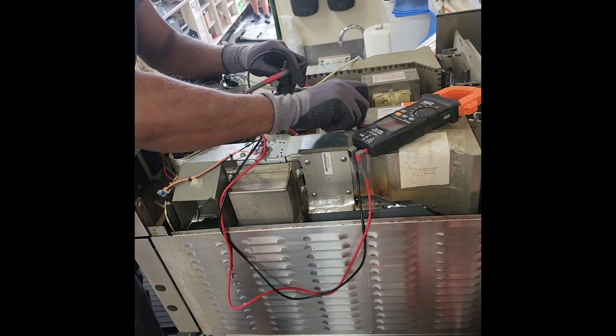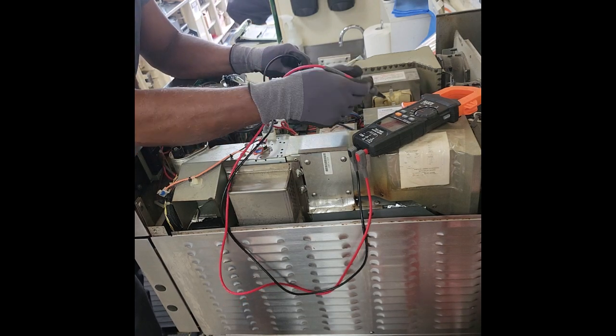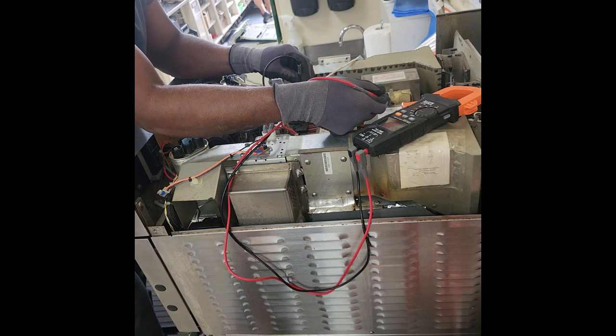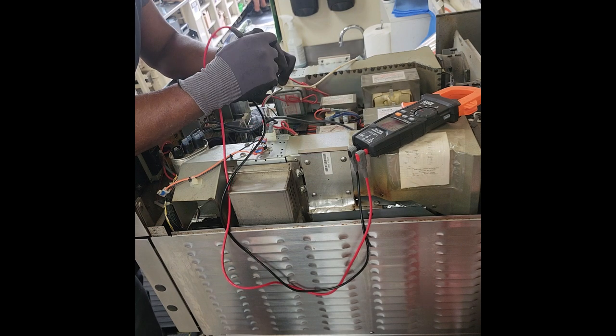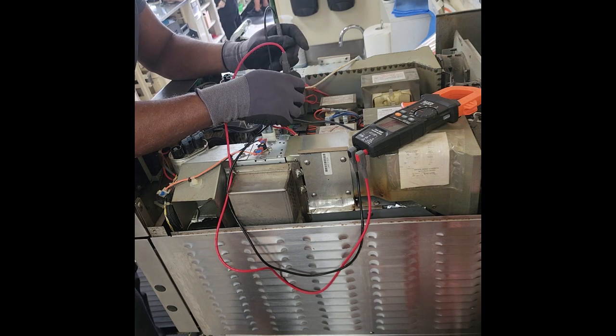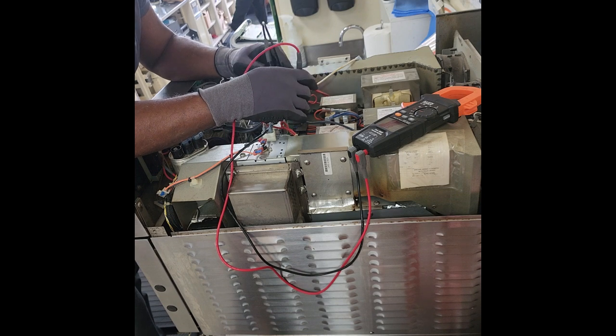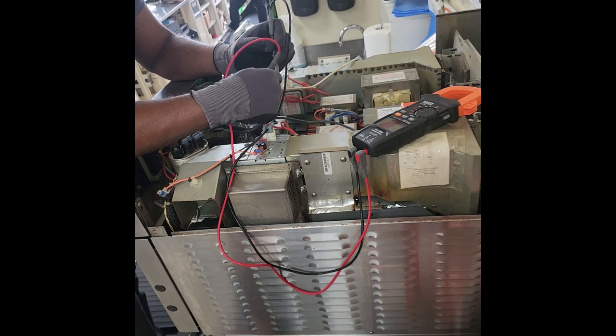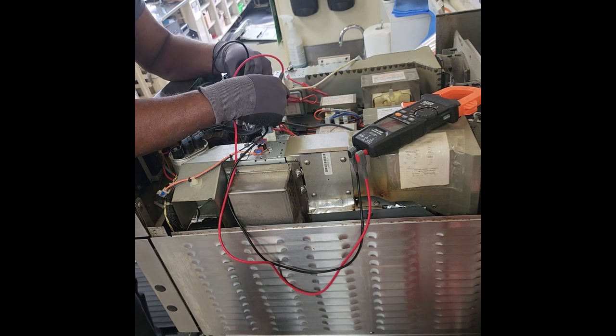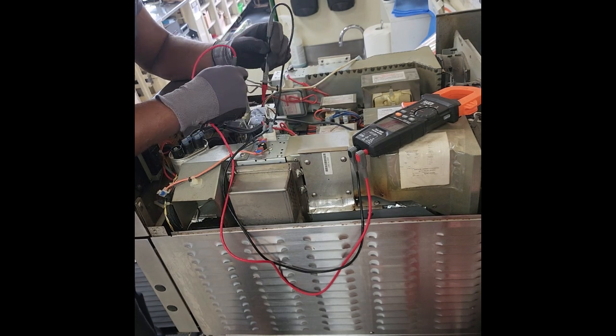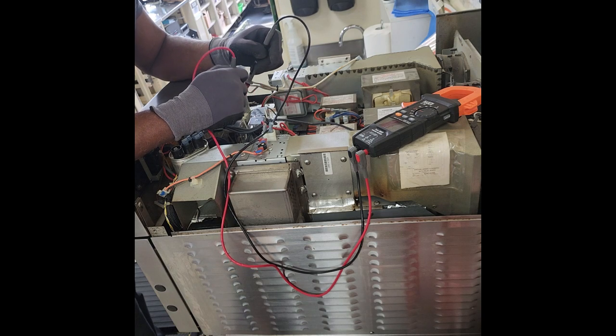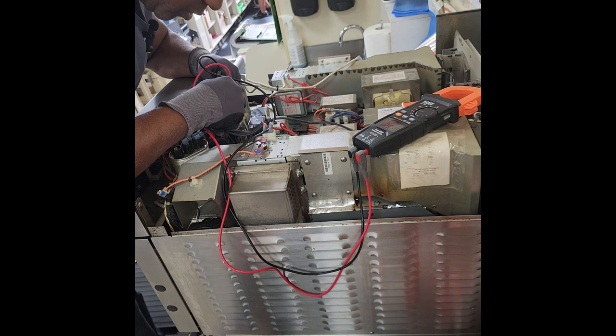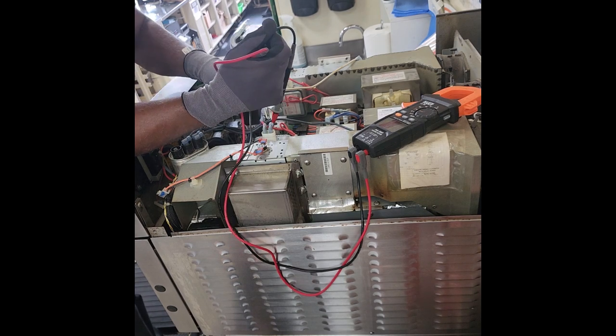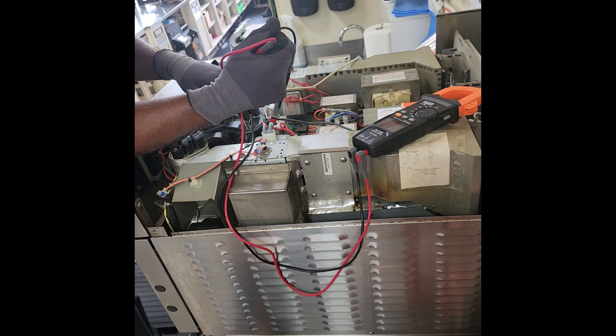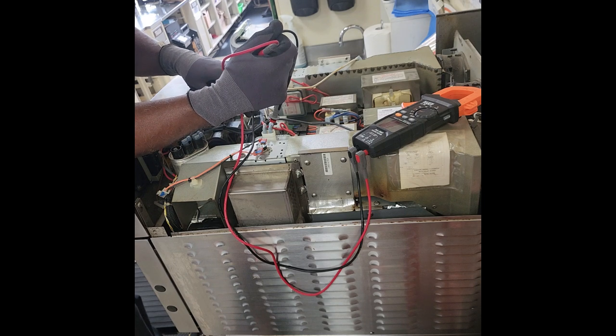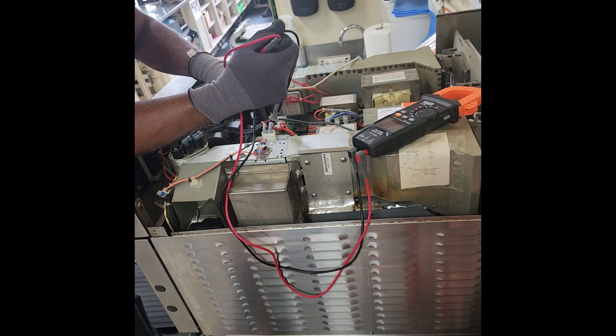Now I'm going to go ahead and check my right side transformer just to make sure that one is good. Yeah, and that one's at 63 ohms. So now I'm going to check my 20 amp fuse, see if that may have blown. That didn't blow. I'm going to check my 12 amp fuse. That's good. Then there's another 12 amp fuse on the circuit board towards the front of the machine, and that one's good. So all of my fuses are good, so that's a good sign, because then at least I know that my K2 relay is good and stuff. So that didn't short out or anything.